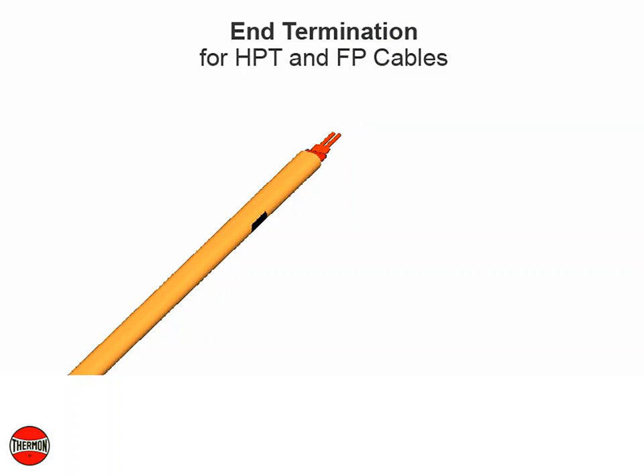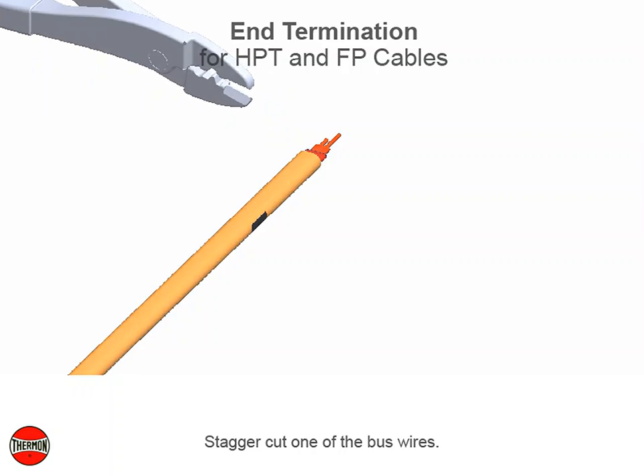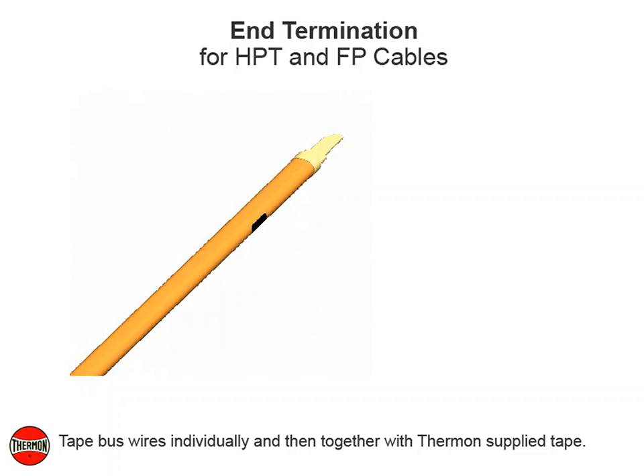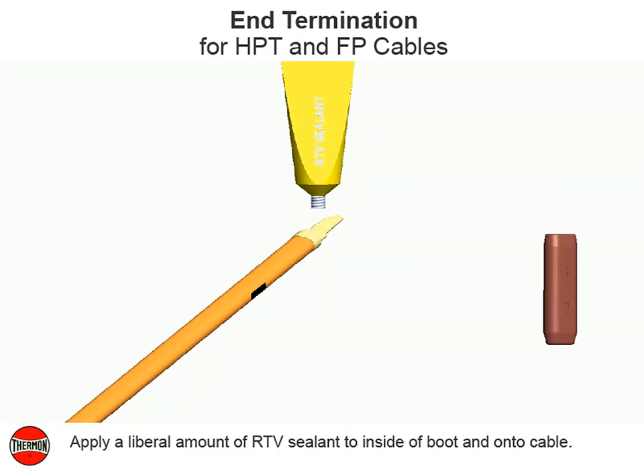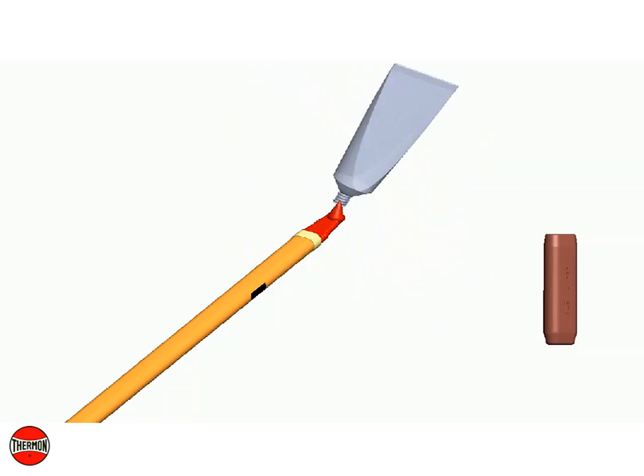Stagger cut one of the bus wires. Tape bus wires individually and then together with Thermon supplied tape. Apply a liberal amount of RTV sealant to inside of boot and onto cable. Slide end cap onto end of cable.